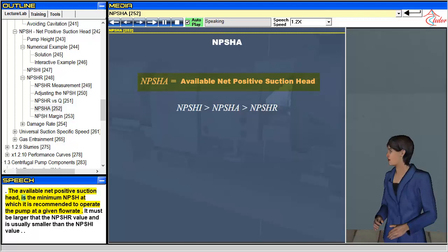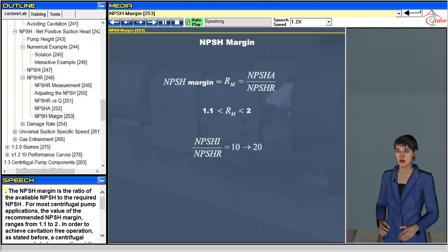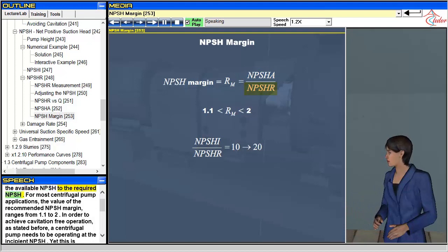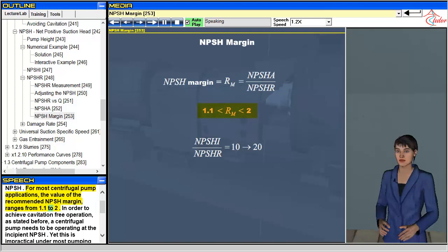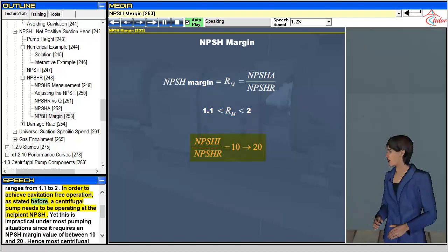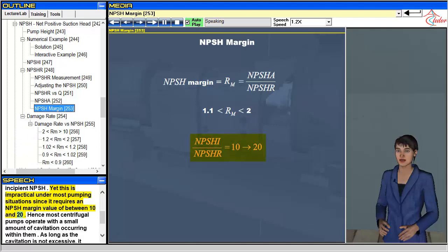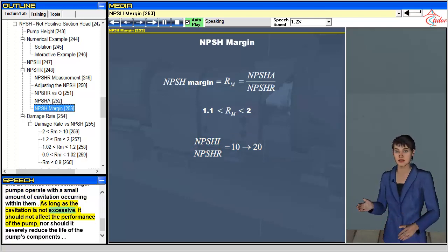The available net positive suction head is the minimum NPSH at which it is recommended to operate the pump at a given flow rate. It must be larger than the NPSHR value and is usually smaller than the NPSHI value. The NPSH margin is the ratio of the available NPSH to the required NPSH; for most centrifugal pump applications this ranges from 1.1 to 2. In order to achieve cavitation-free operation, a centrifugal pump needs to operate at the incipient NPSHI, yet this is impractical since it requires an NPSH margin of between 10 and 20. Hence most centrifugal pumps operate with a small amount of cavitation, which should not significantly affect performance or reduce the life of the pump's components.